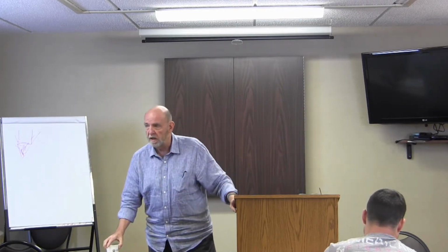I've gone into houses where I had the attached garage. There was just one breaker on the wall in the attached garage, and that was a 200-amp breaker. And then you go into the house, and in the basement I have a panel that has no breaker on it. So that's a non-breaker, but they were using the feed from the breaker in the garage. So literally, my main breaker for the box was the 200-amp breaker in the garage that was installed in a little box all on its own. So if I wanted to kill power to the house, I had to go out to my garage to kill that switch. And that would stop the power in the house. I had no way of cutting it off at the panel or at the box in the basement.